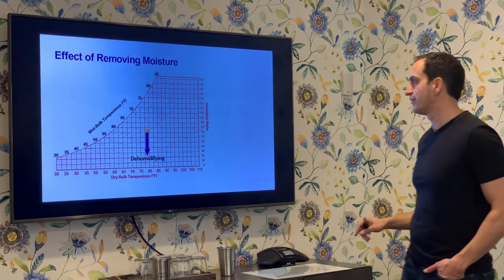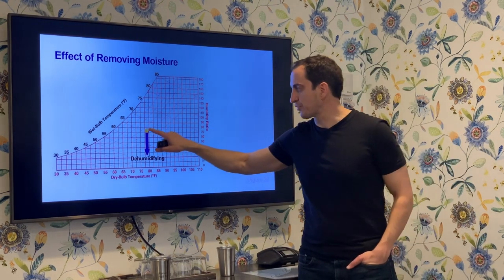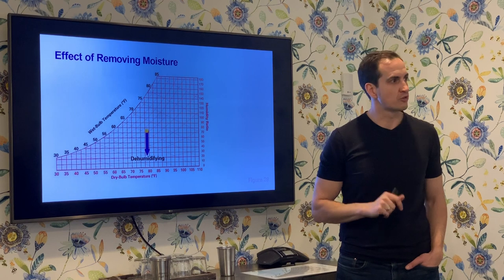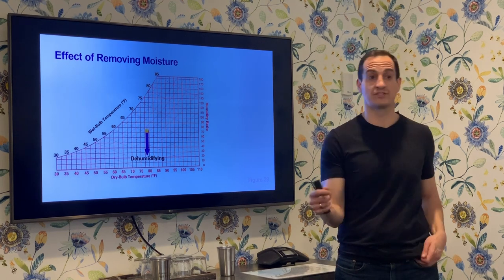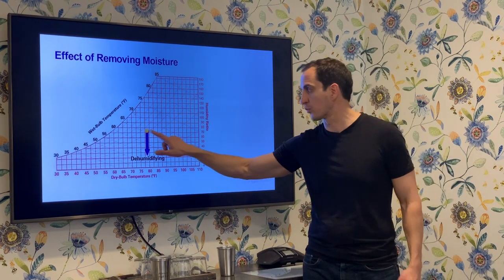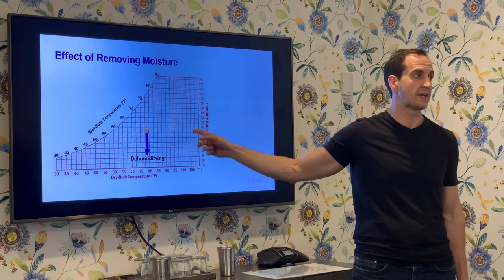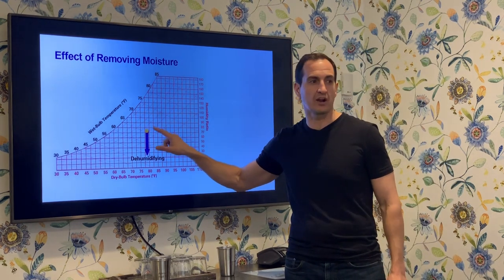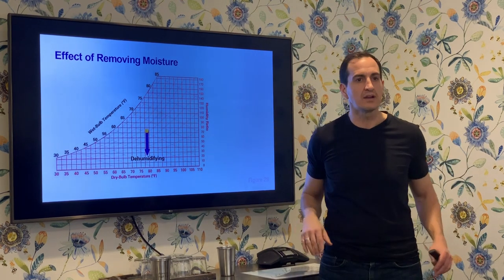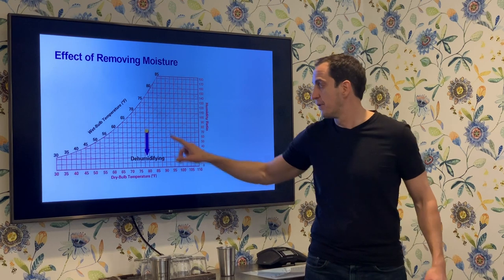To take moisture away, in general I have to go downward on the chart. Going straight down — from this condition to a lower humidity ratio without changing temperature — is not physically possible with any commercially available media for greenhouses or indoor grows. We may end up taking the air through a cooling coil or a desiccant; we may end up at a different point at the end of the day. There's no way to go straight from here to there.